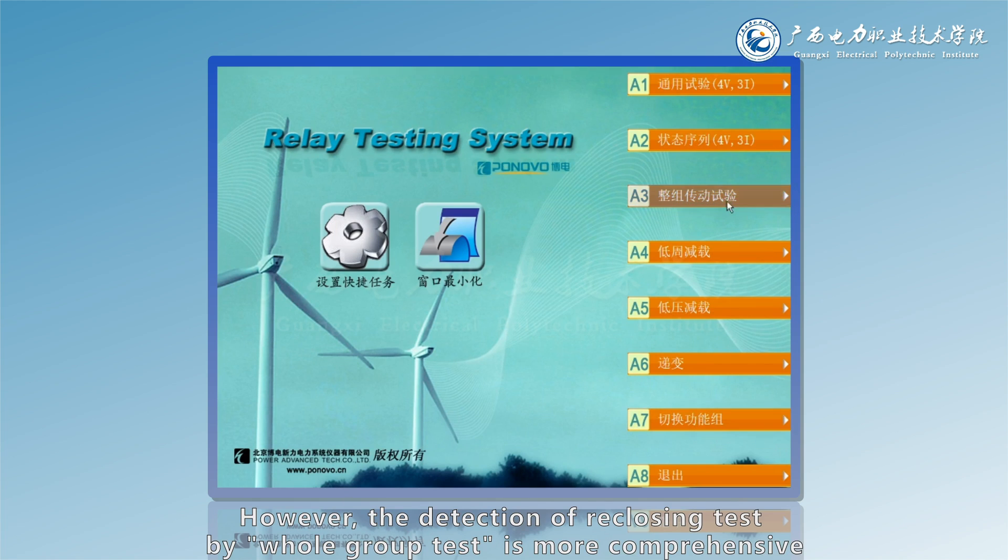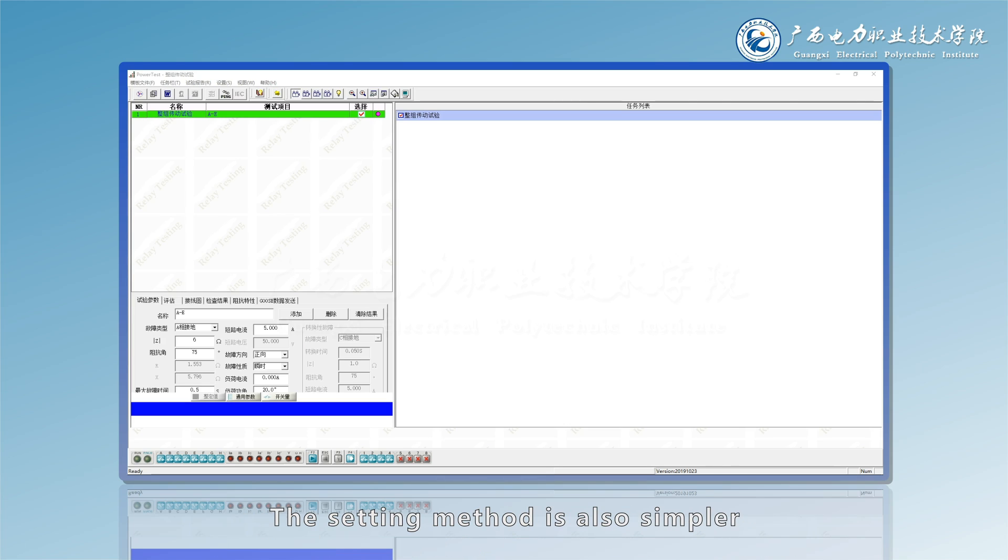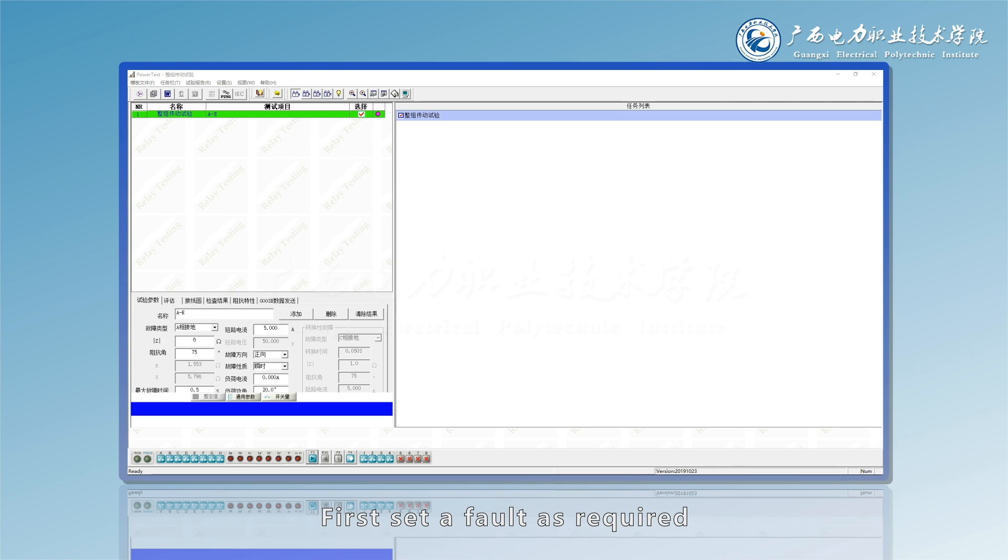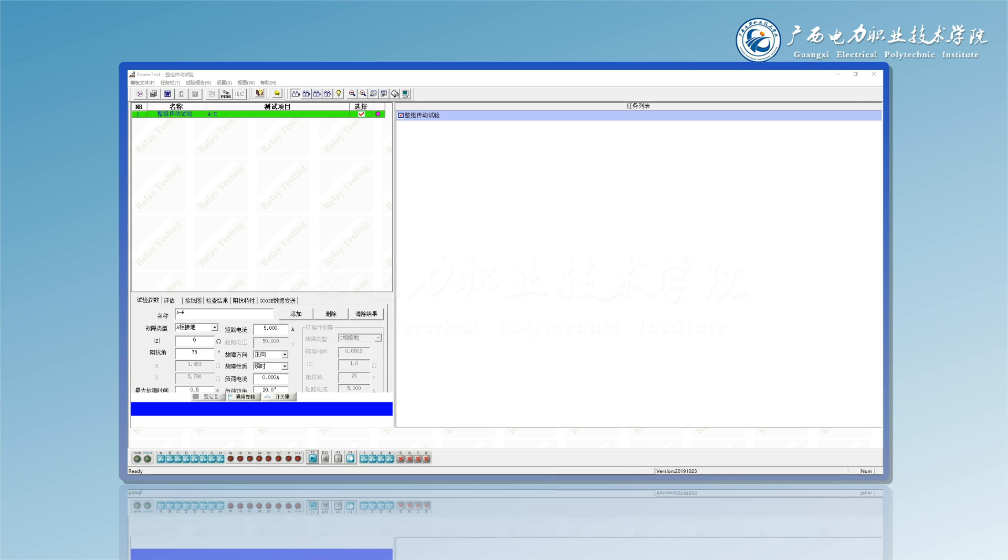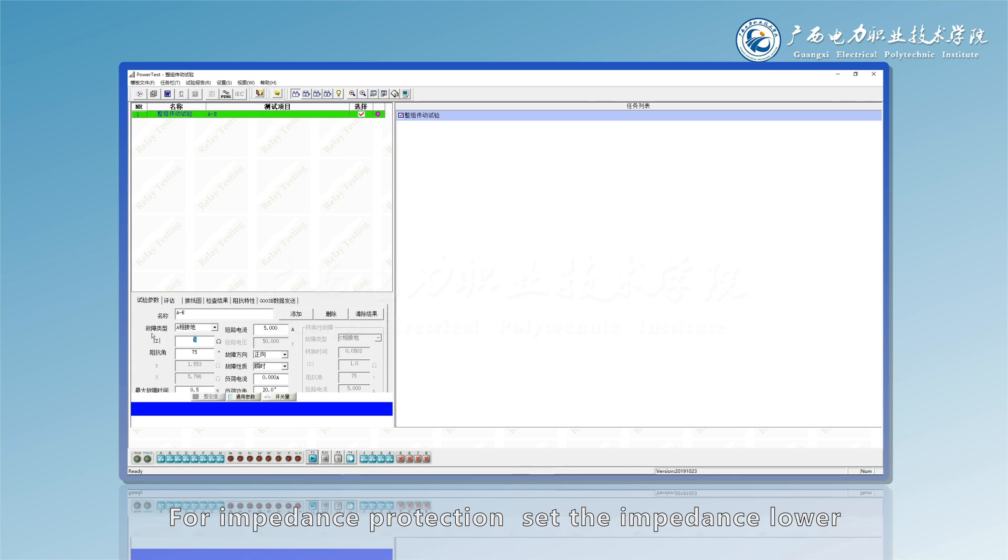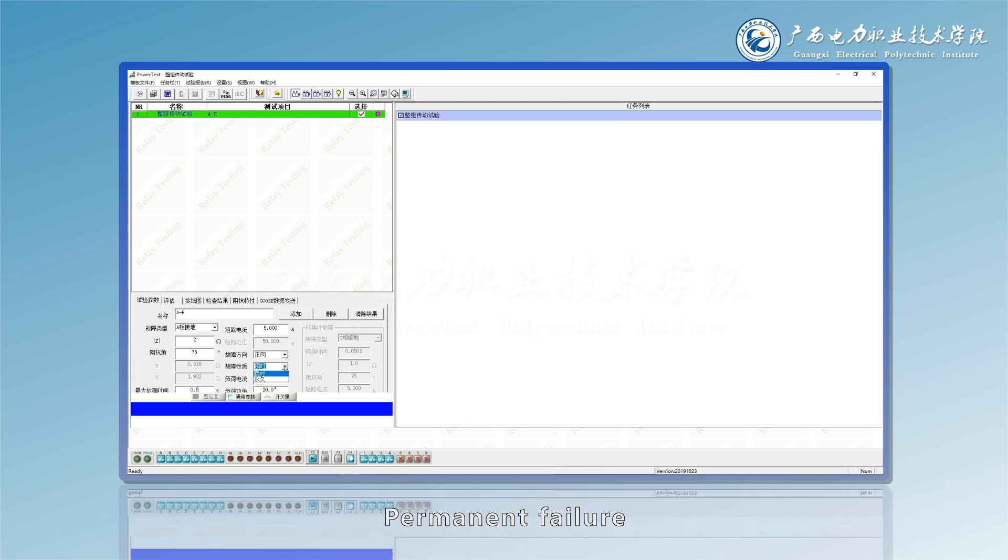However, the detection of reclosing test by whole group test is more comprehensive, and the setting method is also simpler. Its general setting method is: first set a fault as required. For over current zero sequence, set the current higher. For impedance protection, set the impedance lower. Then set the fault type: transient faults can be set, permanent failure, or switching fault.